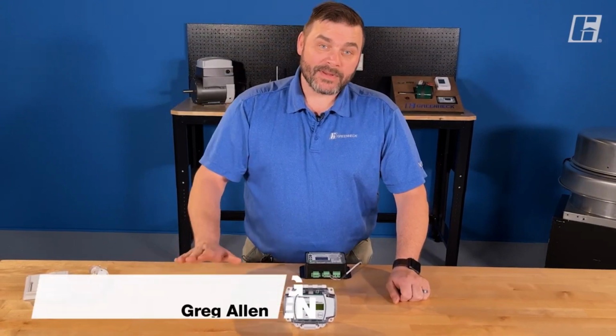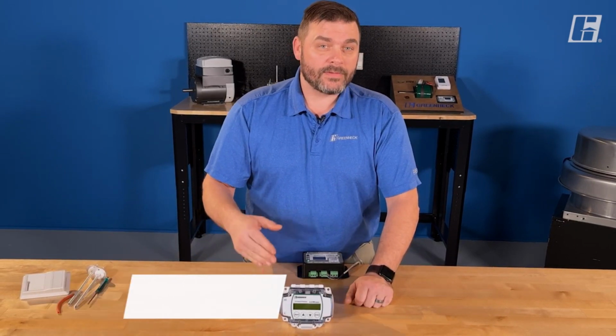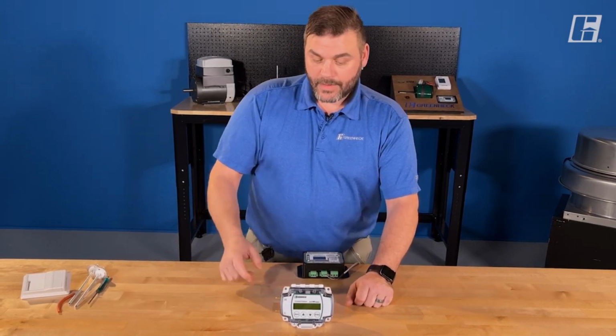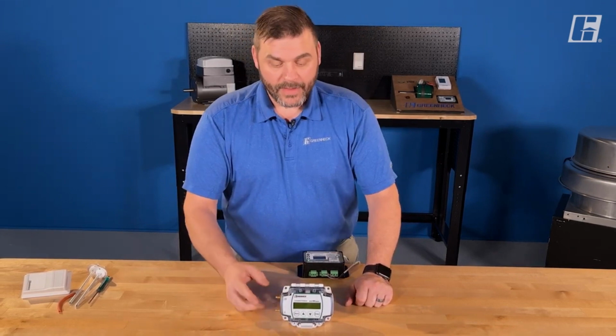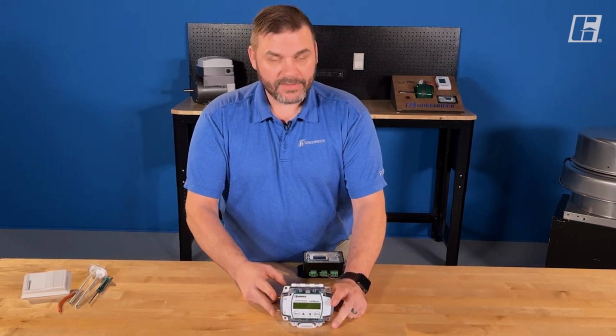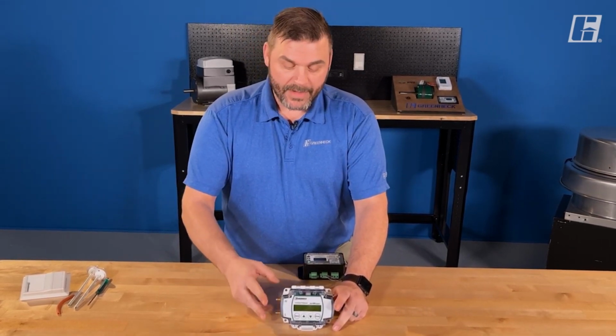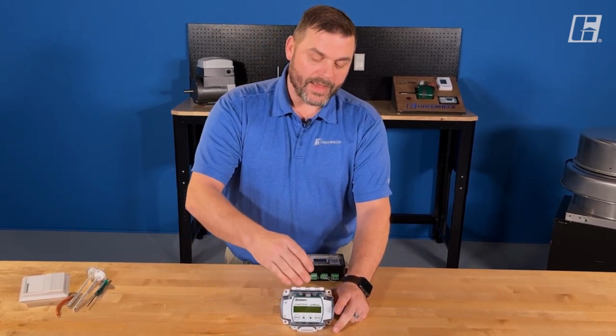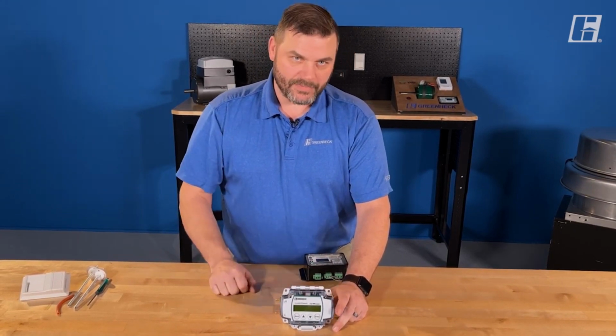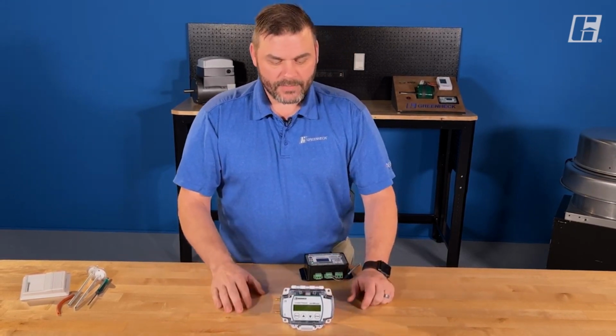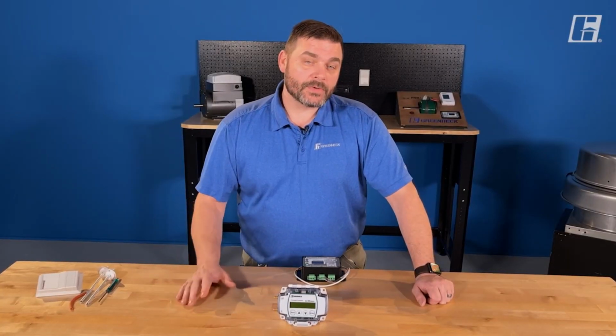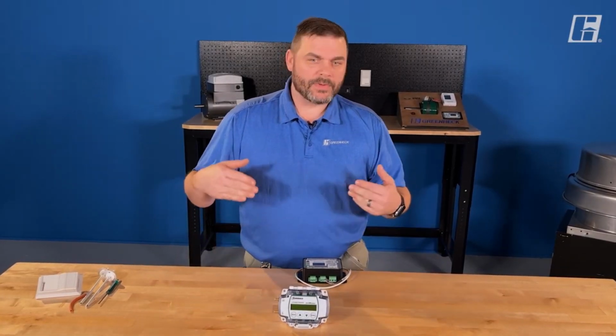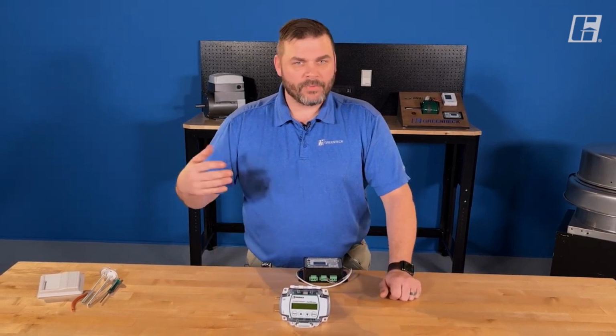Welcome back to the shop. Today, another Vari-Green control to go through. This is the constant pressure controller, or the constant CFM controller. What this will do for you is monitor 2 points of pressure and then control the speed of a fan to maintain that relationship. Now, how could we use this? The constant pressure controller simply will control the speed of a fan to maintain a pressure or CFM point.